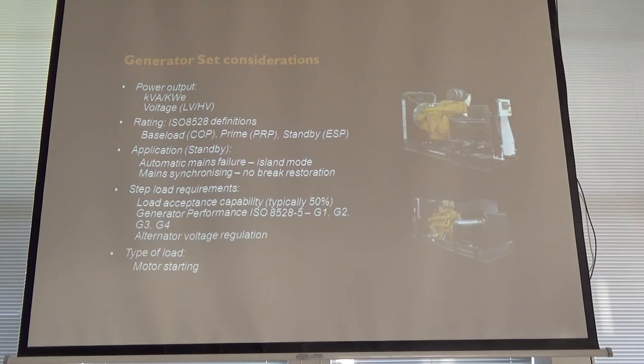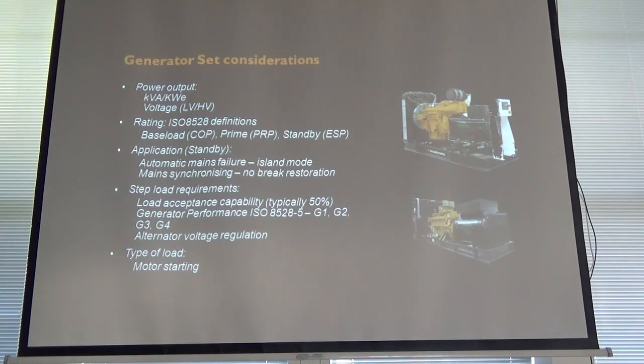In other words, that'll give you 100% load for an unlimited period of time. That tends to really push you towards gas sets, where you want a base generation, you want them running 24/7, and then you might be importing a top-up from the mains for any deficits or maximum loads that you have on a building profile. So often, I haven't sold one diesel set that runs on a COP basis, to be honest.